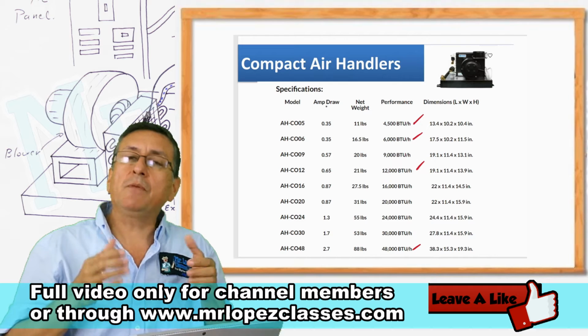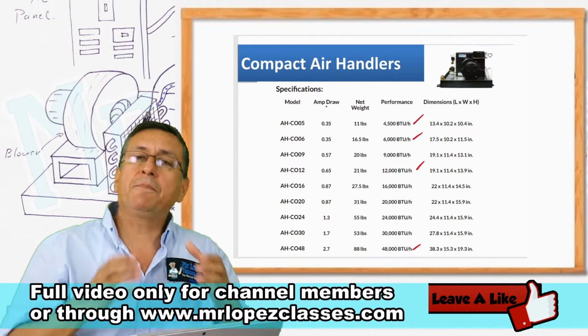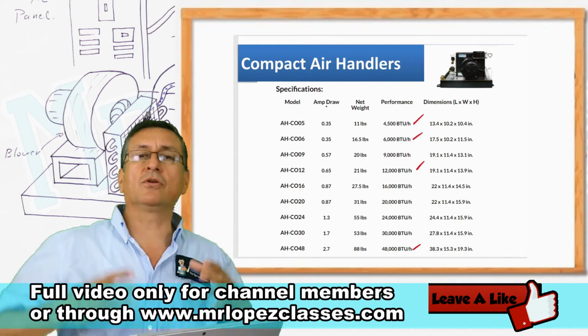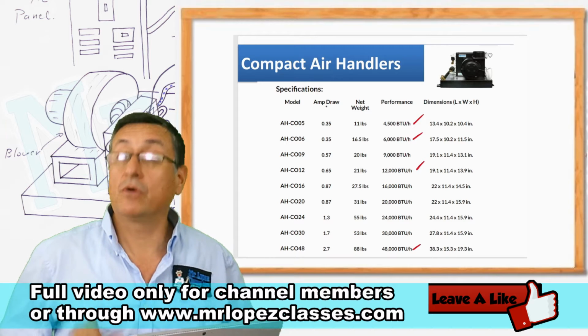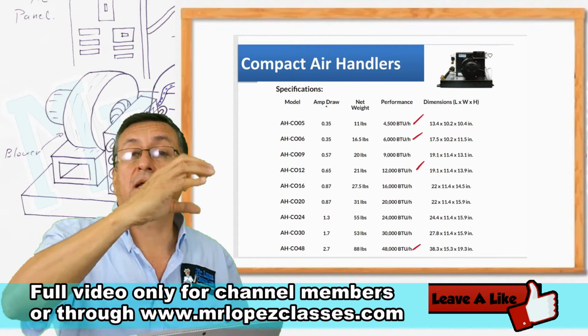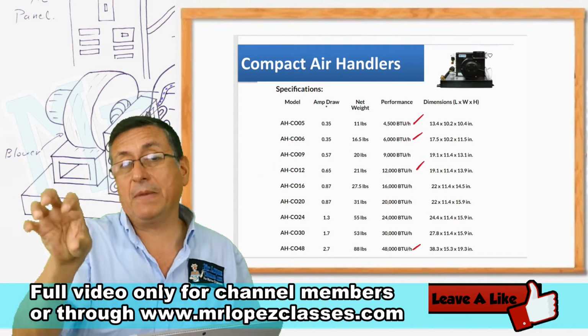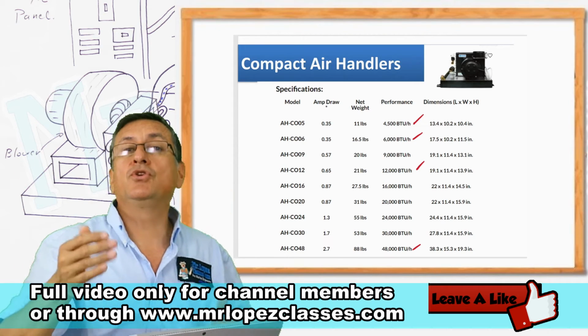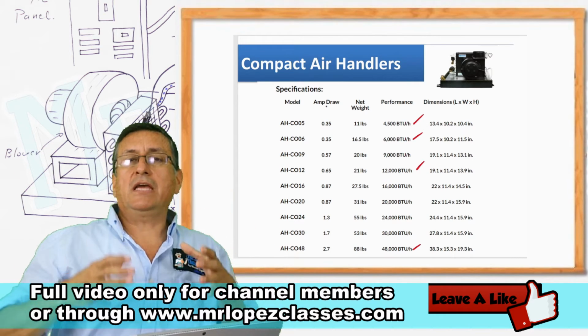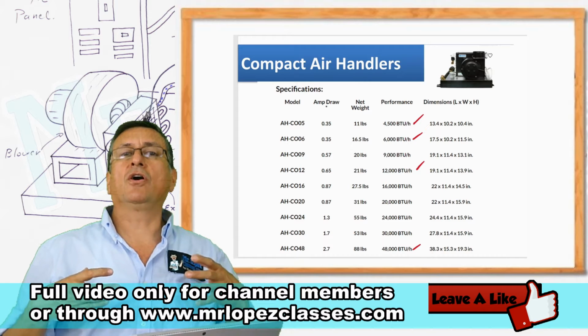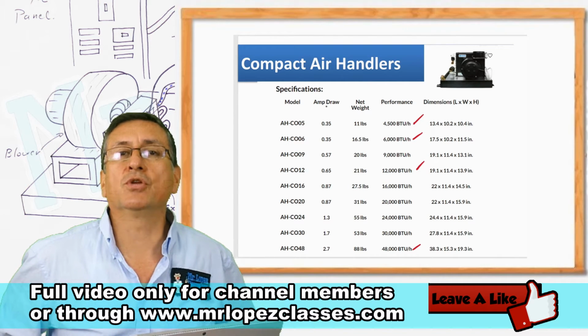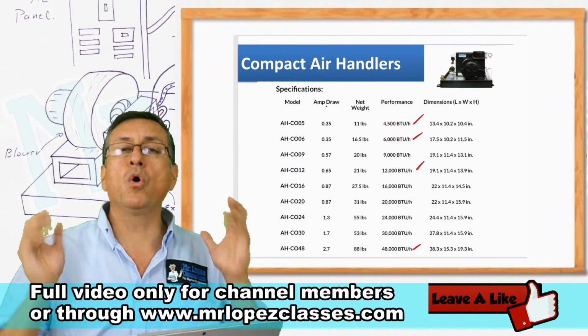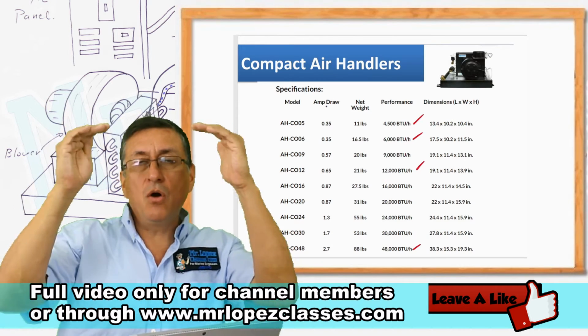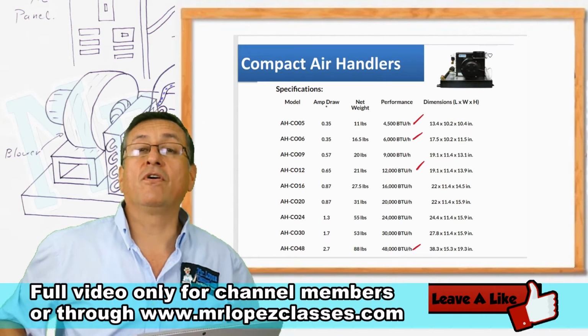Maximum 60,000, but I prefer a little less. I prefer 10% less than the total capacity of the equipment. Is that clear? The addition of all the capacities of the air handlers should be maximum 90% of the total capacity of the central chiller unit, in order to work below the curve of efficiency.